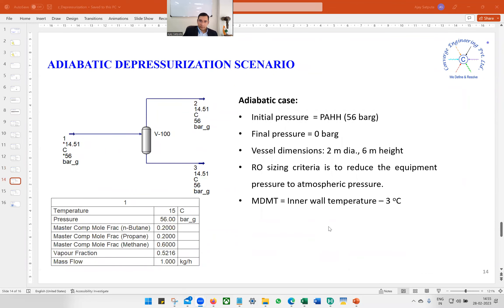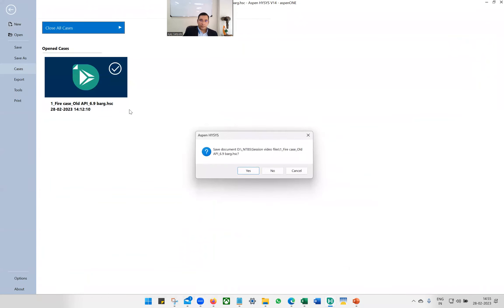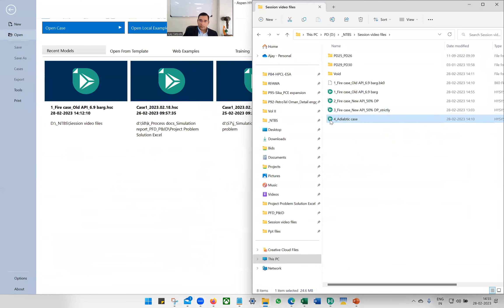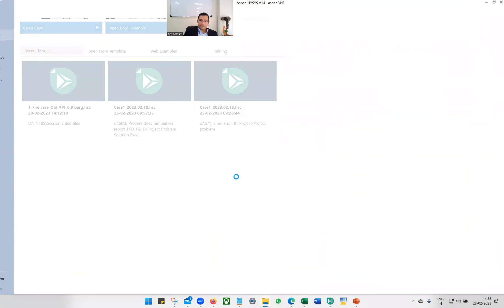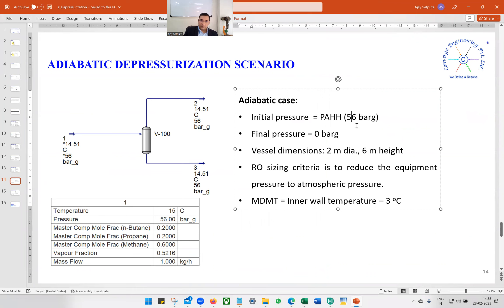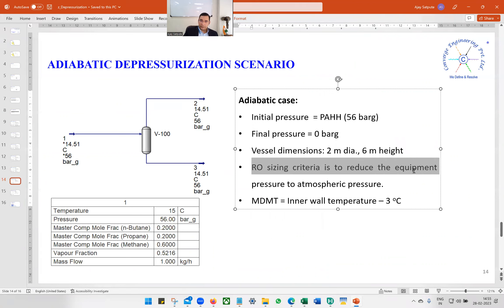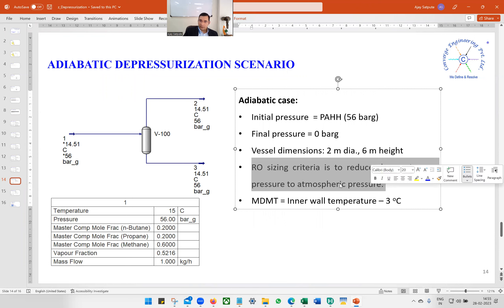Now let us move to the adiabatic case. The initial pressure is PAHH — let us assume 56 bar gauge for this case. Final pressure would be zero bar gauge, assuming we are sending gas to atmosphere. Vessel dimensions remain the same. The RO sizing criterion is to reduce equipment pressure to atmospheric pressure, and we are not in a hurry — if it takes a couple of hours, that is fine.